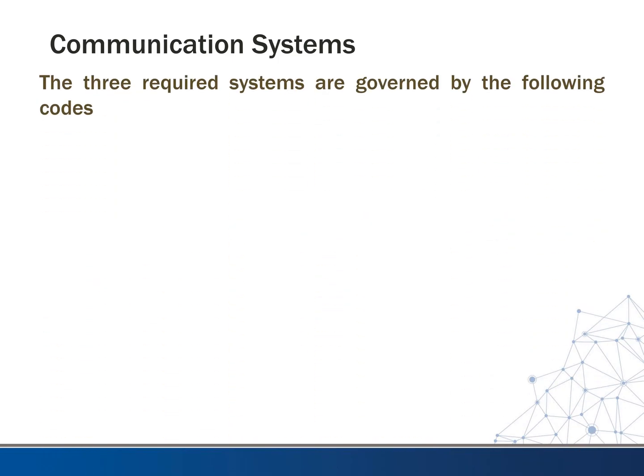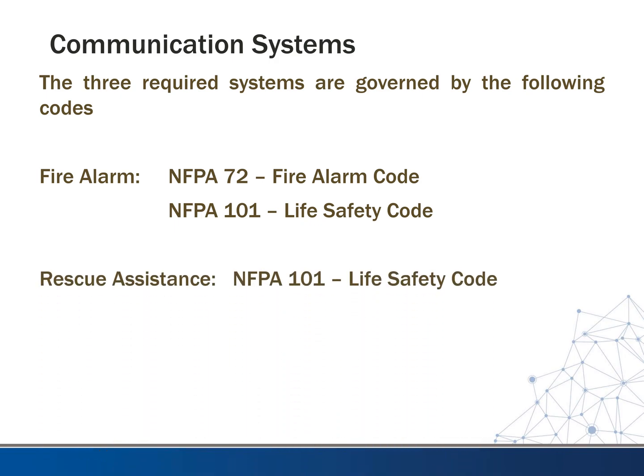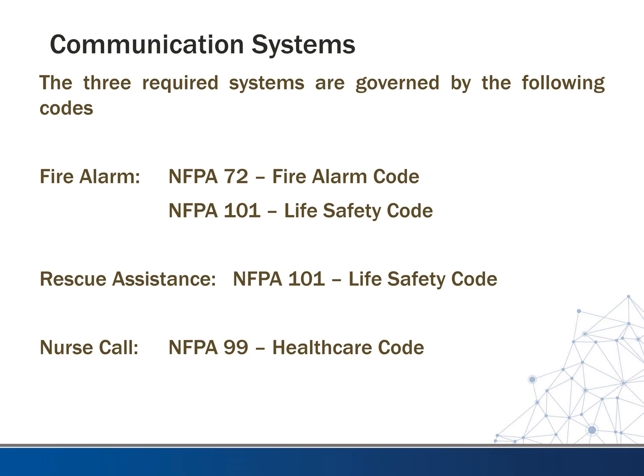The three required systems are governed by the following codes. You'll need familiarity with NFPA 72, which is the fire alarm code — remember the National Electrical Code is NFPA 70, so NFPA 72 is the fire alarm code. You might also utilize NFPA 101, the life safety code, which has language about strobe location and rescue assistance. Nurse call is covered in NFPA 99, the healthcare code.